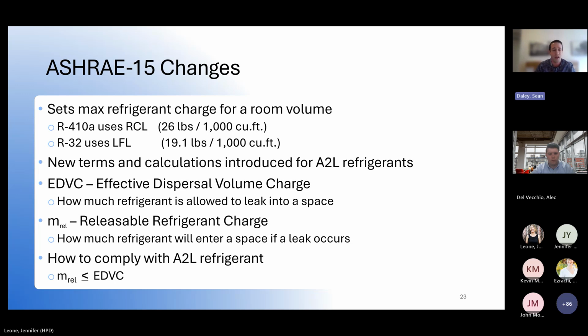The next term is MREL, or releasable refrigerant charge, and that's how much refrigerant will enter the space if a leak occurs. In the past, with R410A, if a leak occurred, we had to assume the entire refrigerant charge was going to leak into that space. Now with the A2Ls and the introduction of leak mitigation, that's not the case. So it helps us comply with this standard.